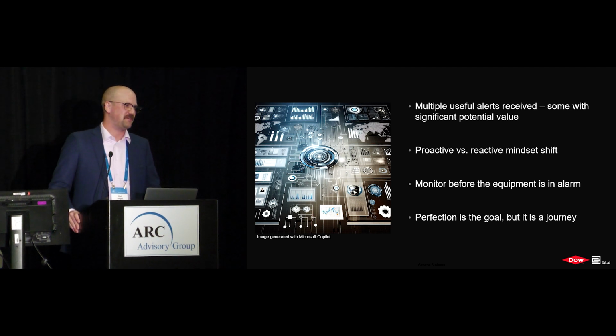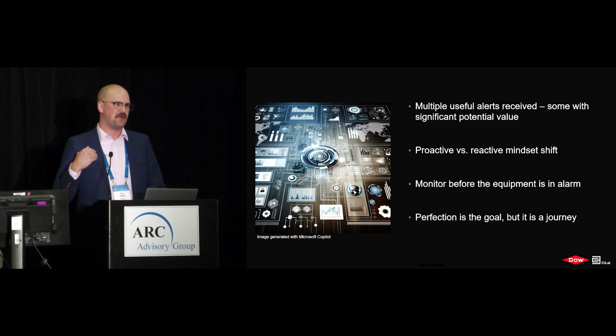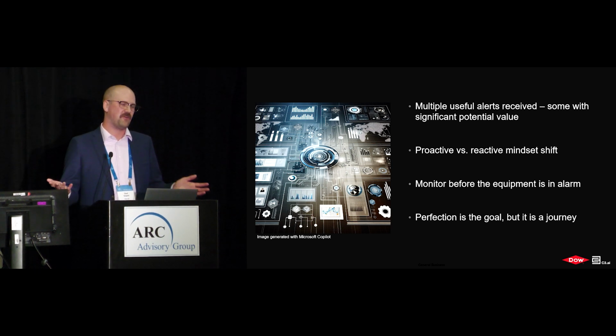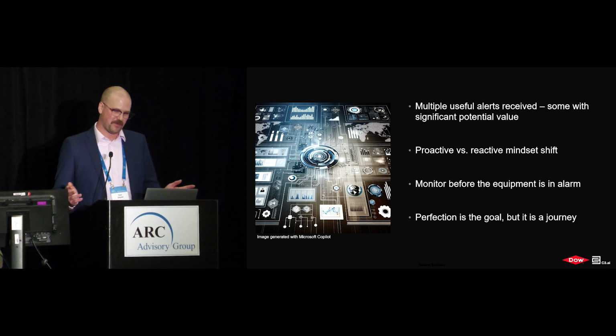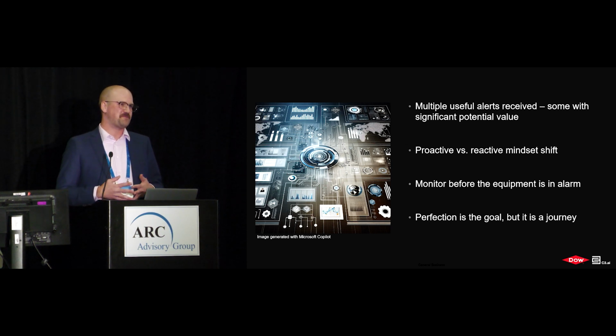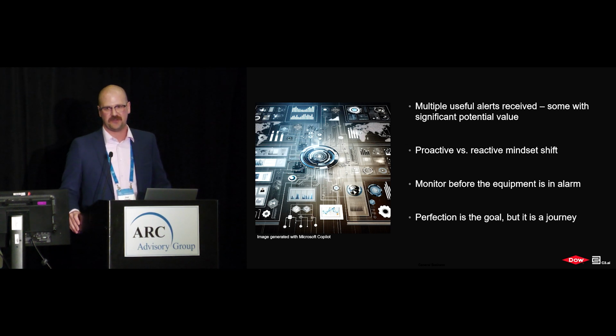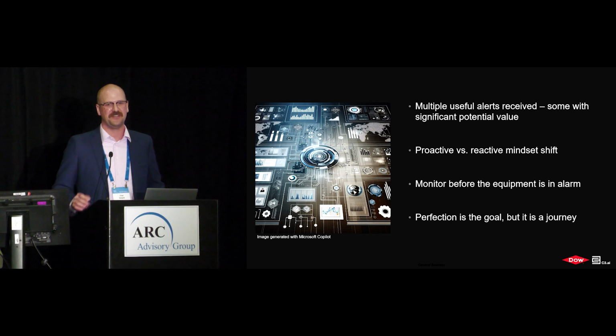And so we would be running rate restricted until we get to that next furnace window. This is where the application has allowed us to detect this issue and take action to slow the fouling or in some cases even reverse it. So this is probably our first potential event. It's still under investigation, but this is the first potential event that has that multi-million-dollar impact avoidance, so we're watching it pretty closely, and we need to be able to correct that course.